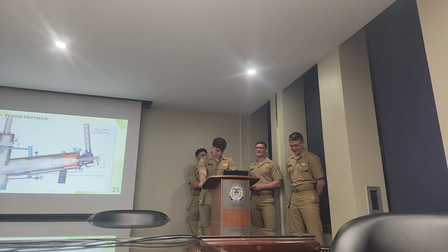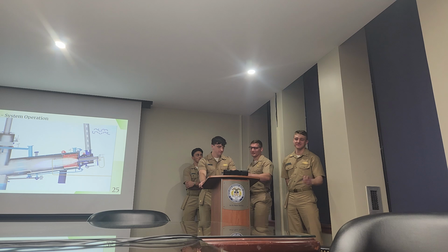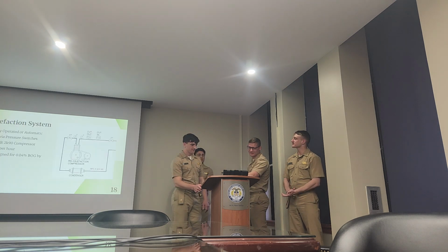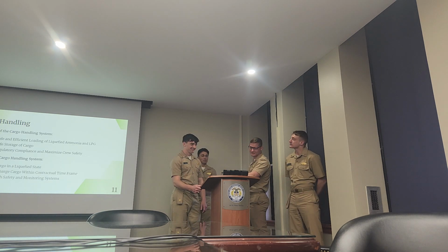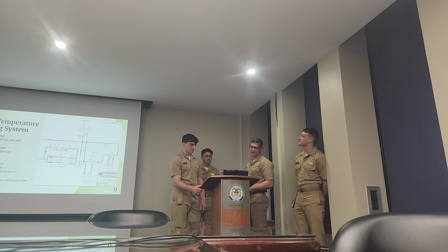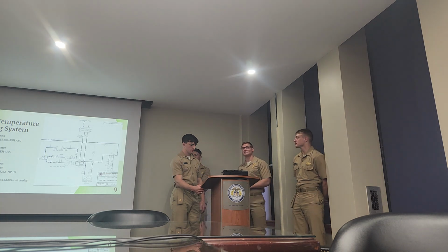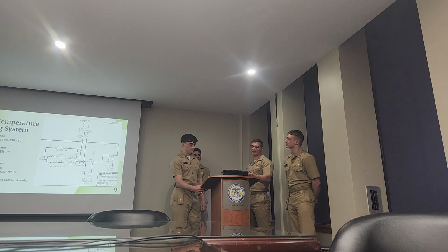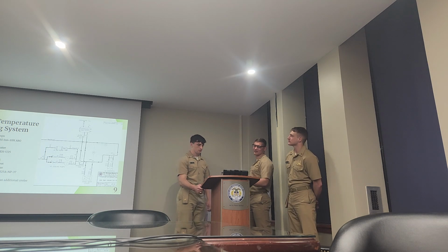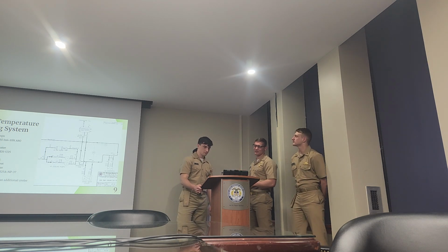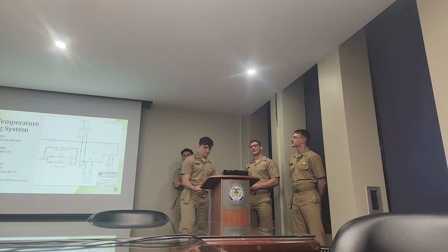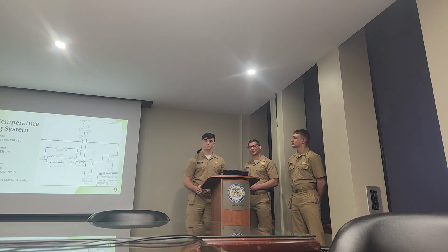The manufacturer. ANC, I believe it was. I have it. And let's just say there's a supermarket that has pumps for sale. Do you think there actually is gonna be a 57 horsepower on the shelf there for you? Yes, sir. Okay. Well, I have the pump here. It's an 811 ANSI. I can see what it says there, but my point is that there's no such thing as a 57 horsepower motor.